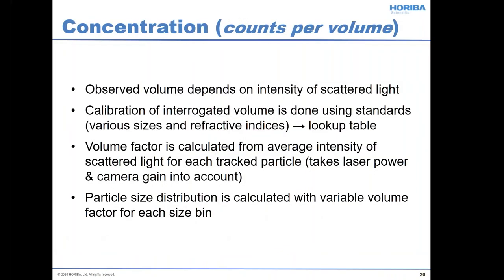Moving on to concentration, which has come up with a fair amount of interest when people look at virus-type samples. The challenge is that your observed volume actually depends on the intensity of scattered light. Your observed scattering volume is smaller for small particles that scatter weakly compared to large particles that scatter strongly. So you do need to do a calibration of observed volume as a function of particle size, and once you know that, we can calculate the size distribution with the correct scattering volume for each species or size.